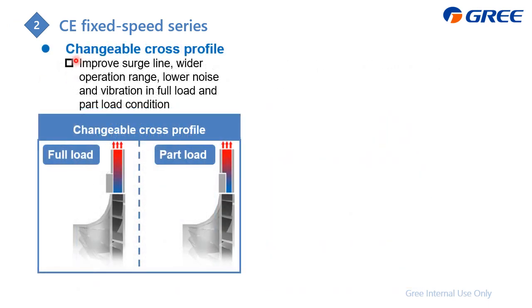Next feature is the changeable cross profile. What is it? During the full load condition, this discharge is fully open. During the part load condition, you can find this one just moves direction, and this can lower the discharge area. The benefit of lowering this area is that the discharge pressure can be higher, right? And with this, we can raise the discharge pressure, which avoids or lowers the surge potential.